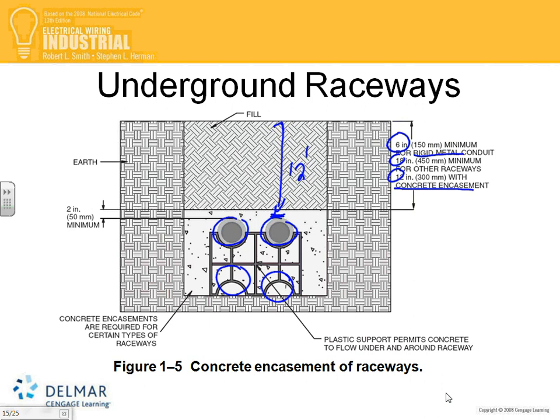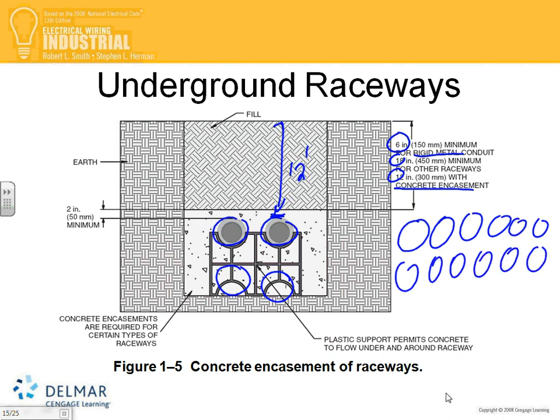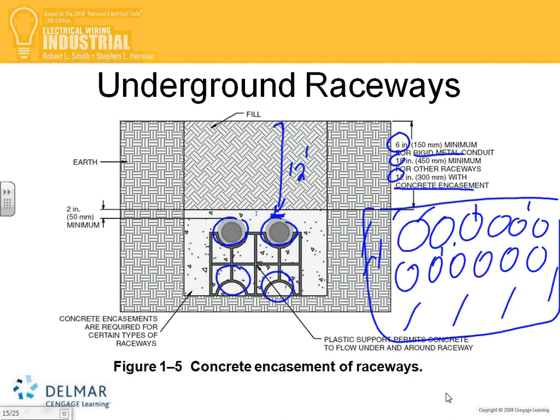You need to pour concrete around. Yeah. They set them with this frame, and then pour the concrete around it, concrete encased. Where would they use something like this? The 4,000 amp switchgear that you guys are going to be having, most likely you're going to end up with 12 runs of 500. So here's 1, 2, 3, 4, 5, 6, and 1, 2, 3, 4, 5, 6. This is a system where you build it, encase it in concrete, and bury it at 12 inches. Each one is PVC. I think it's probably 500 kcmil to get you the 4,000 amp. Off you go.